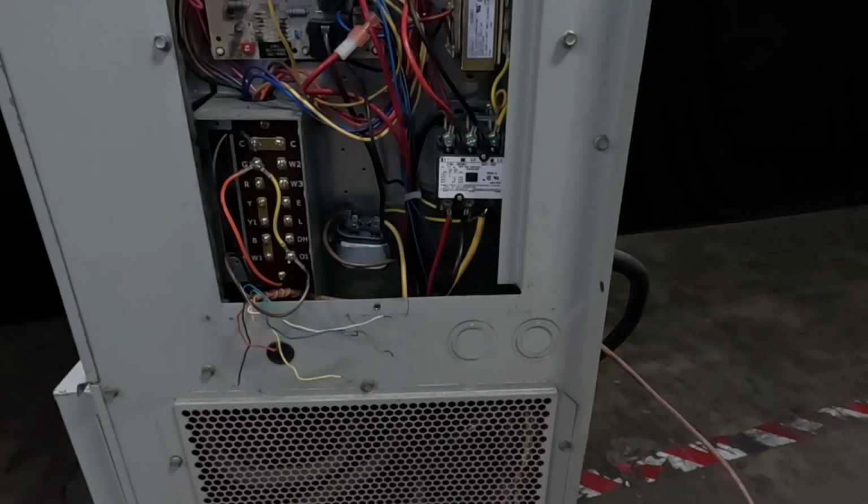If you still have the same issue, disconnect any other wires connected to the front of the low voltage terminal block. Those are generally ventilation devices. Retest the mode having trouble. Did this test identify the ventilation device as the problem? If the unit works correctly in all modes, then you have eliminated the unit as the problem. Now go on to the stat wire, or controller.